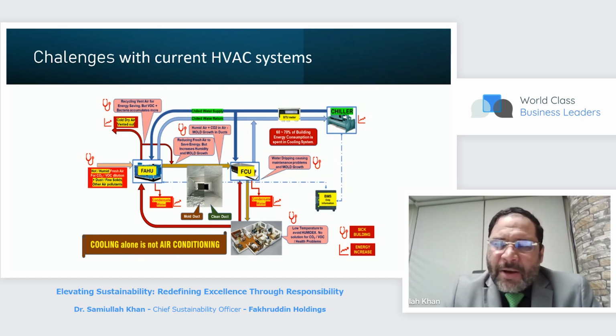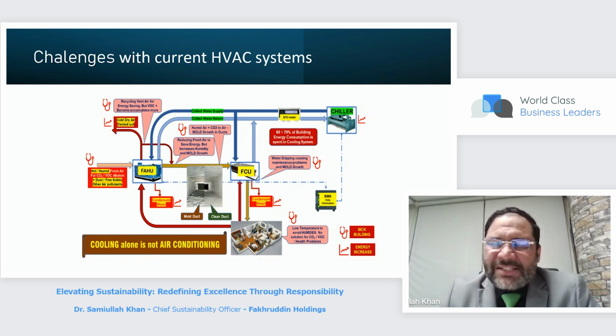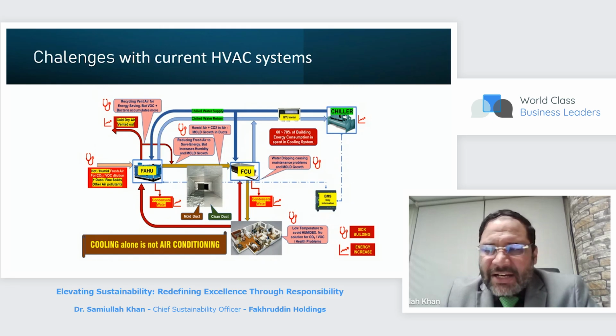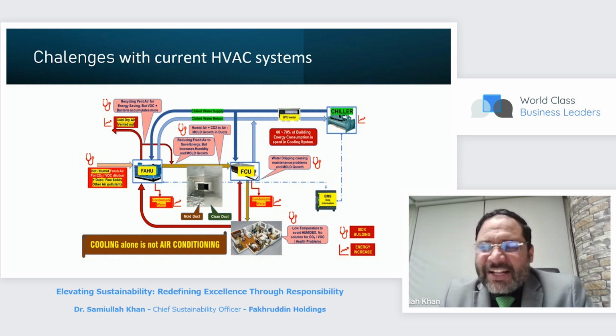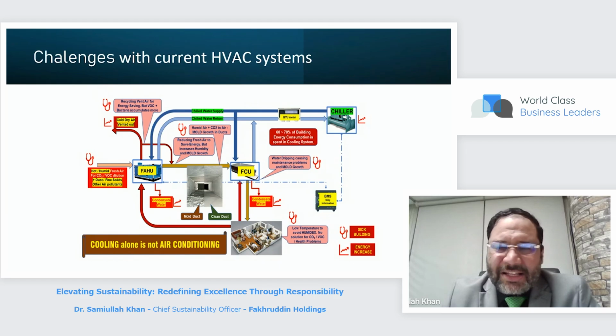And what we noticed is more than 90% of the buildings in UAE and in Dubai are over-designed, because during the design stage, people look at the maximum occupancy of the building at the highest ambient temperature. Now, these two aspects are mutually exclusive, we know by experience, because normally during summer, people go off and the occupancy in the building, whether it's office or residential, is low, and the ambient temperature is high. But in winter, when the air conditioning requirement is lesser, that's the time we have high occupancy in the building.